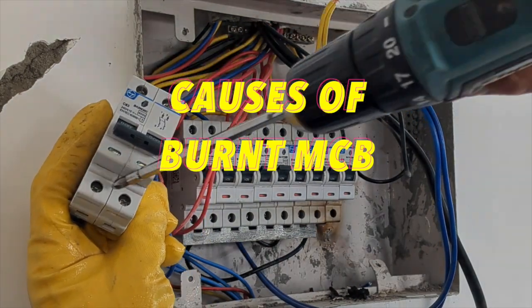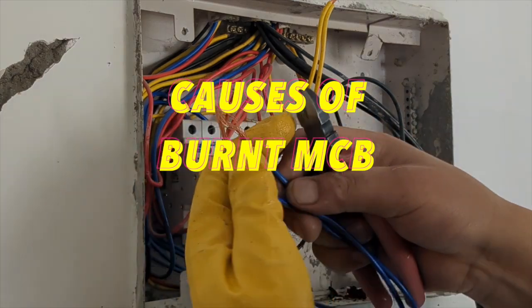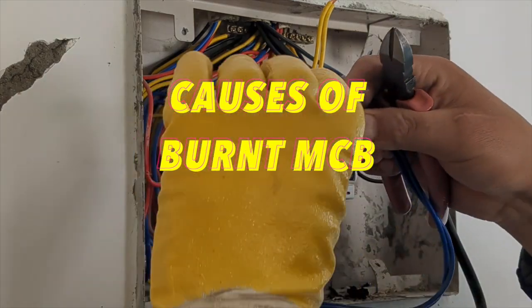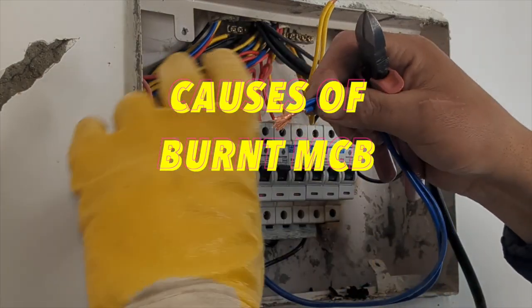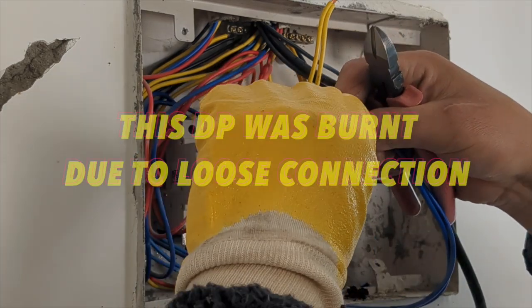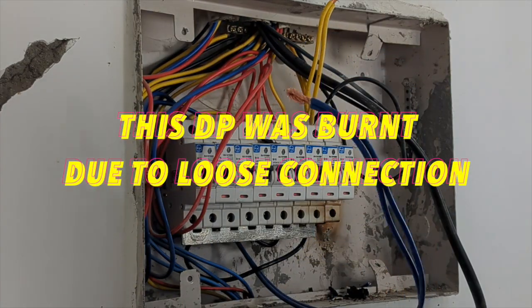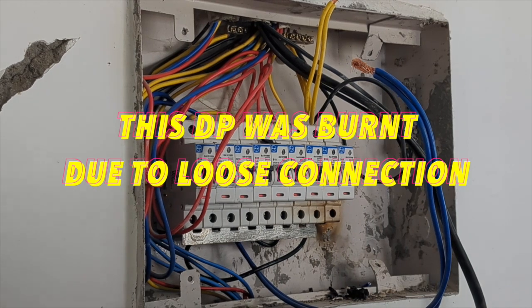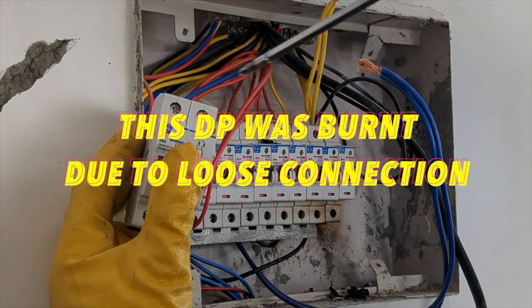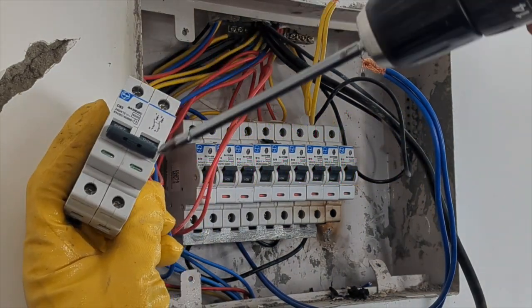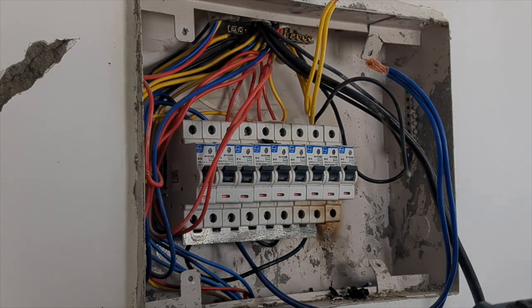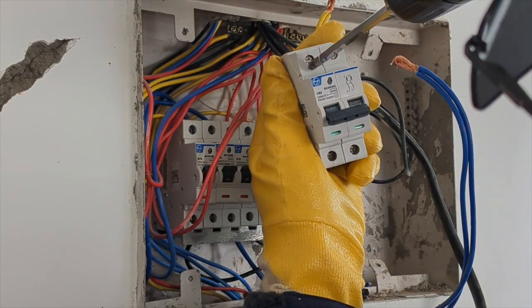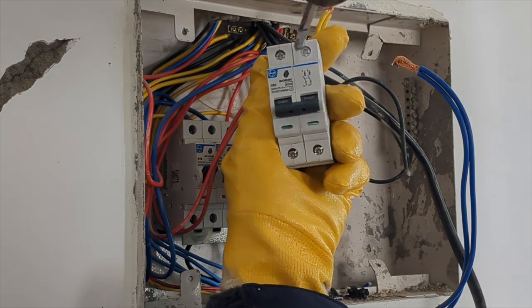Corrosion and moisture can also cause burn in your circuit. This may occur if the breaker panel isn't properly secured or there's a loose connection in it. This one is burnt due to loose connection only. Lastly, faulty installation can also result in a burnt circuit breaker. This can happen if there's a loose terminal connection with your circuit breaker or bus bars, or if an incompatible wire and breaker size is used.